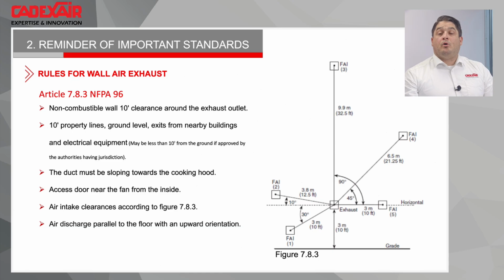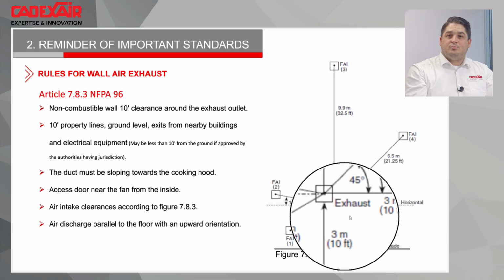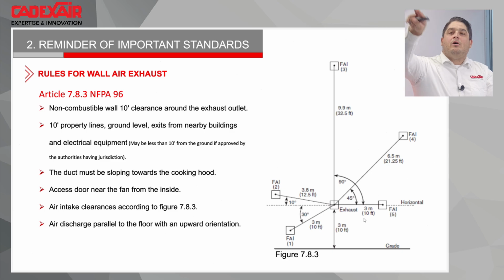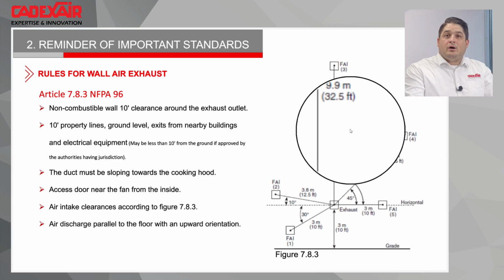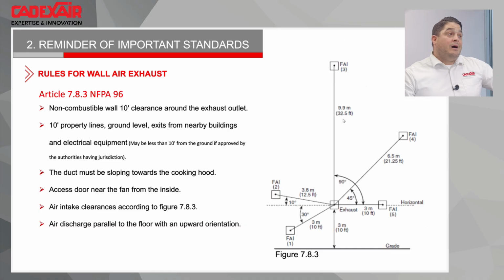I will say there are a lot of pollution control units that can help to reduce that, but the difficult part is that, as per code, it's not written down in the code. If you have a pollution control unit, you will be okay for all the fresh air intake. After that, you need to double check with the authority having jurisdiction. So, a quick recap: 32.5 feet on top, 10 feet left and right, and 10 feet everywhere at the bottom of the exhaust point. There's a formula with the angle, but that gives you a good idea. As soon as you exhaust on the wall, you need to have no door or operable windows on the wall you want to exhaust.